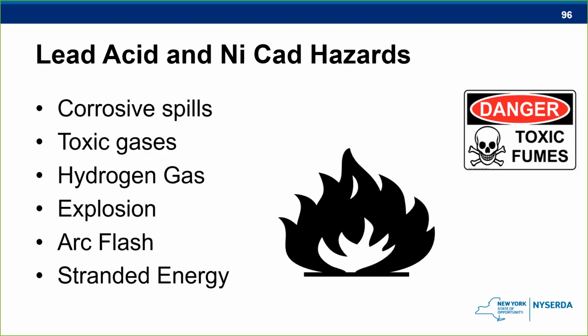So just keep that in mind. I've had that on numerous occasions, wasn't sure about it, and then sure enough, we did some experimenting and figured it out to be hydrogen is cross sensitivity with your CO detector. Explosions are always a concern. Whenever you have a hydrogen explosion, they're pretty nasty explosions. So making sure that everything is being pulled out of the system or pulled out of the room itself, the hydrogen, so we don't have any type of explosion.